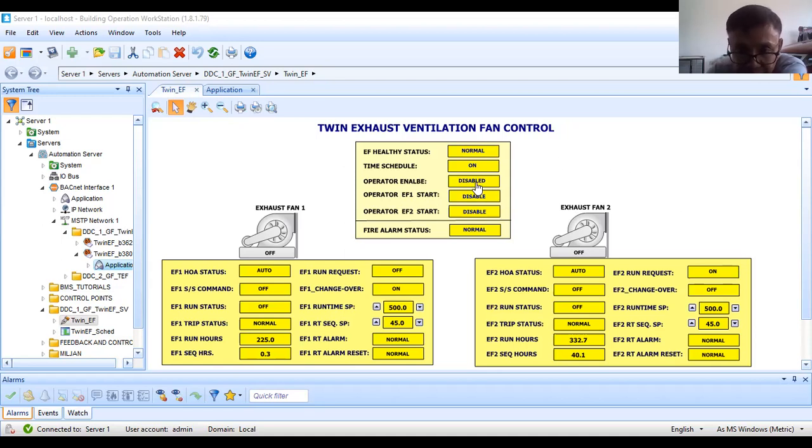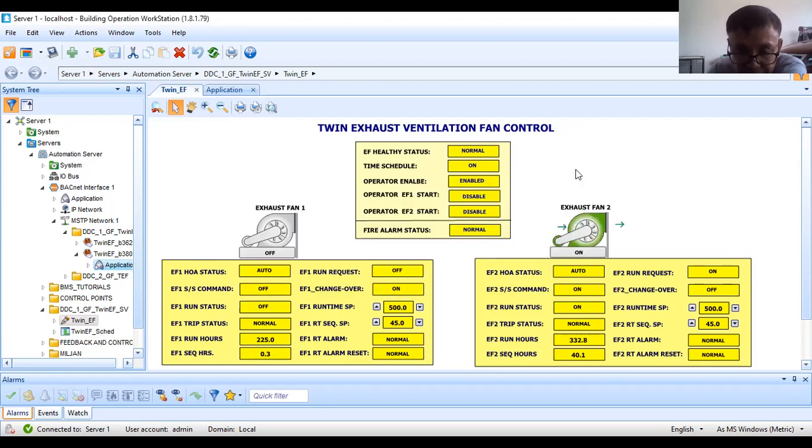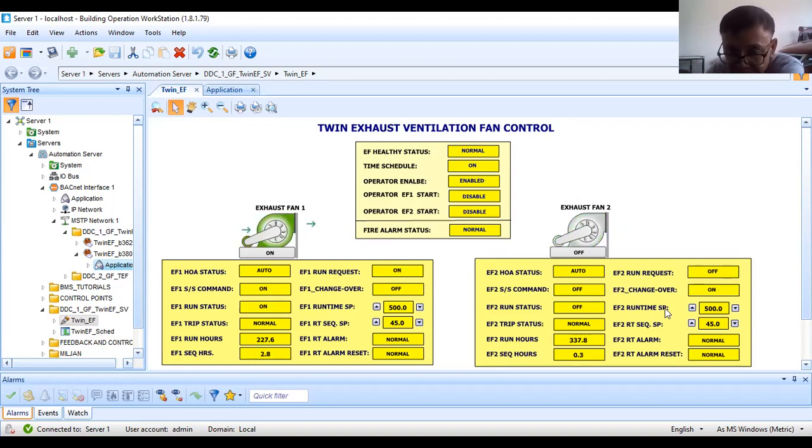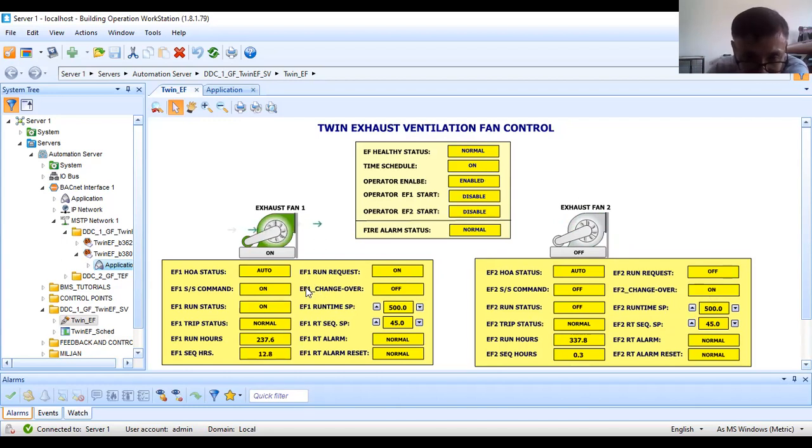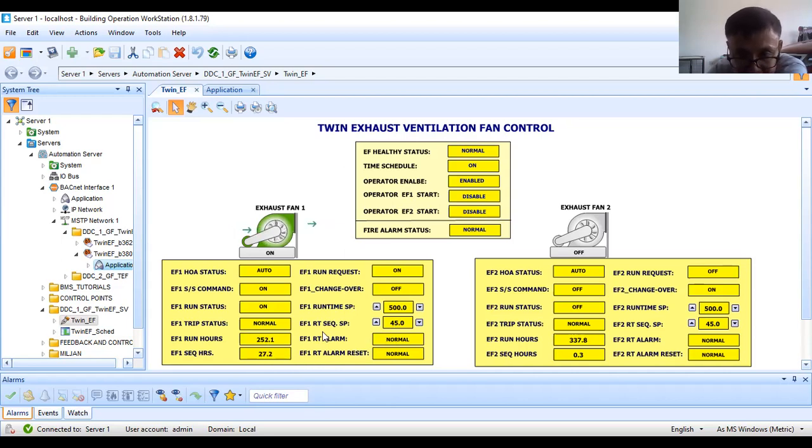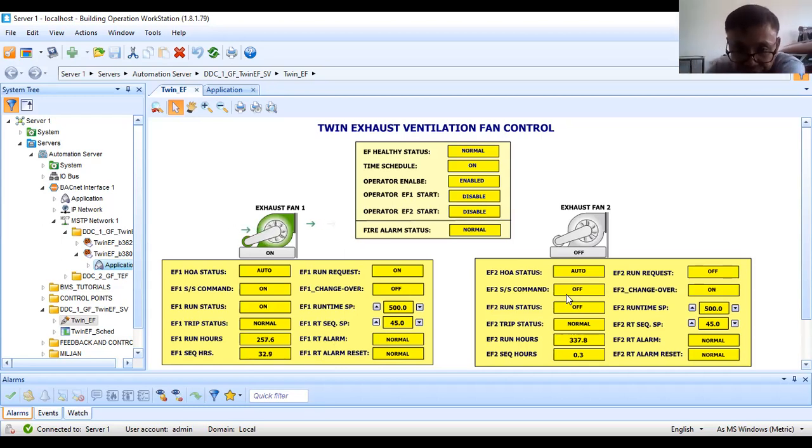Let me simulate. The operator disabled the system, so I will put it online. As you can see, you can hear in the background the energizing of my contactor. So EF2, since it was running before I started this tutorial, now it's changed over. EF2 changed over is on. Now EF1 is running here.